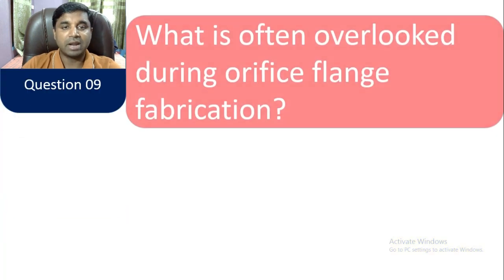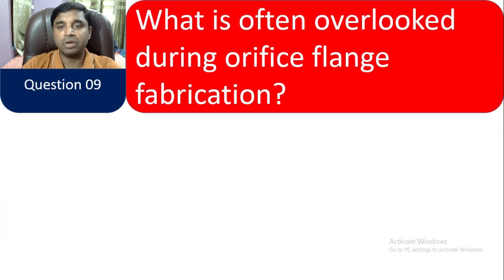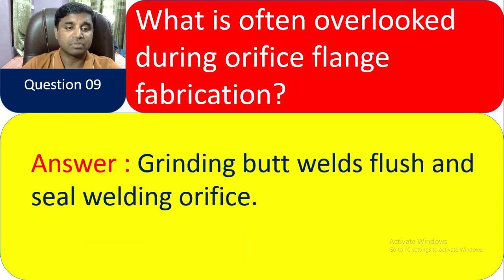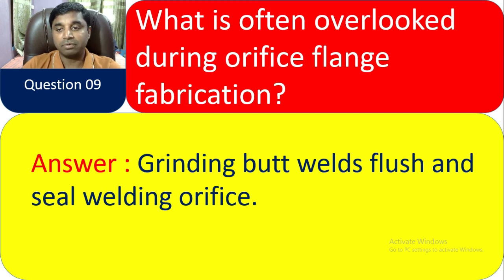Question 9: What is often overlooked during orifice flange fabrication? The answer is grinding butt welds flush and seal welding the orifice. You have to grind the butt welds flush and also grind the seal welding on the orifice.